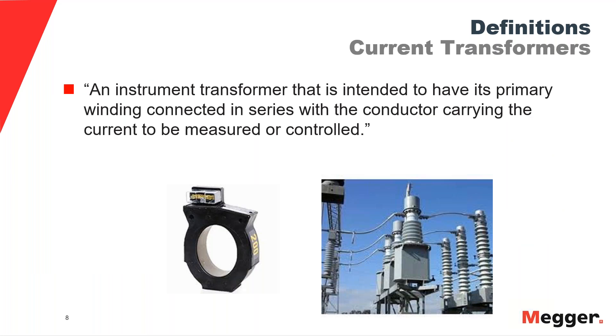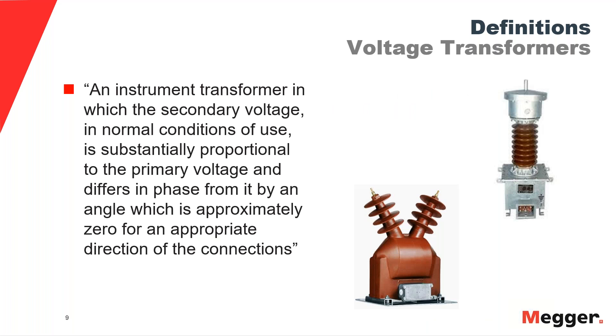What is an instrument transformer? These devices are intended to transmit an information signal to either a measuring device or circuit or a protective or control device. The instrument transformer is intended to have a secondary circuit with a definite and known portion of the current or voltage in the primary circuit to which they are connected. That secondary quantity — either voltage or current — should have a phase relationship with respect to the primary.